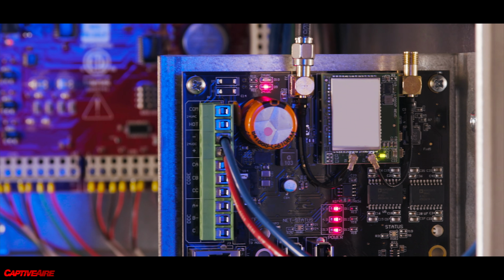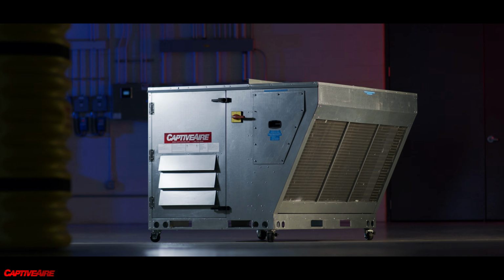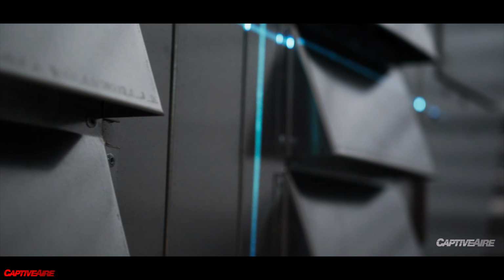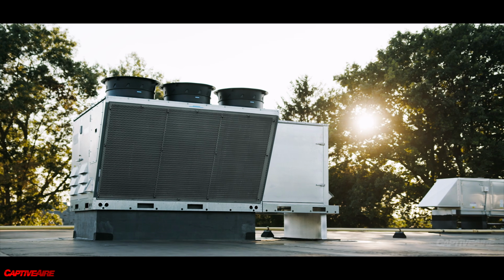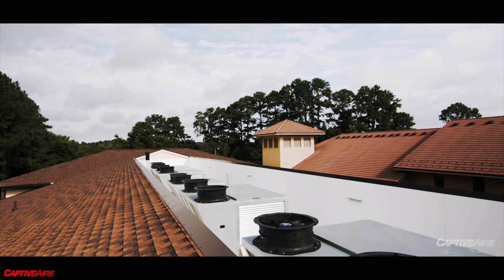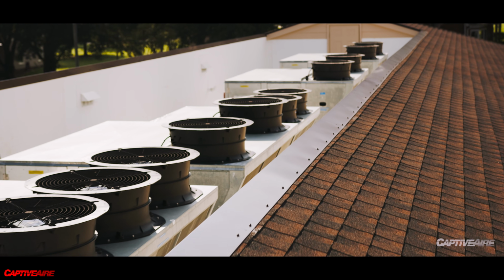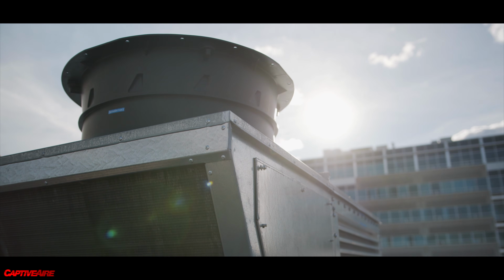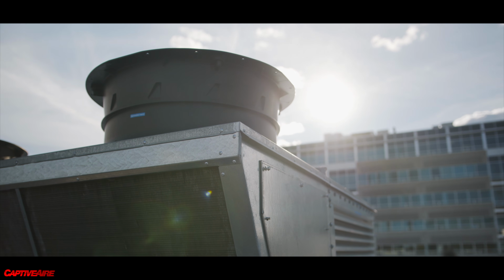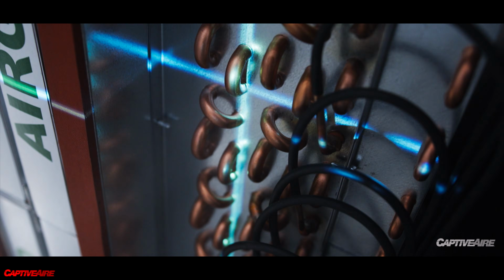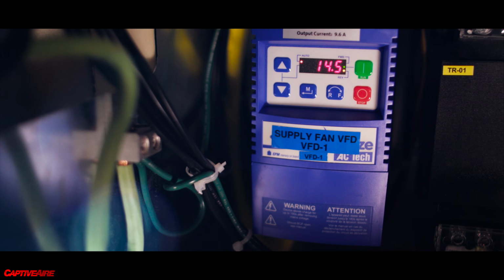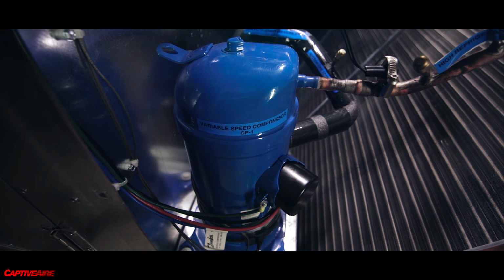This software works with all of our products, but today we're choosing to focus on how CASLink is used to monitor and control our Paragon HVAC units. Paragon is a product that's evolved over the years for us. And from the onset, we were looking at designing this around being a true dedicated outdoor air system, or a DOAS unit. Meaning, all right, we can handle 100% outside air, and everything needs to be able to modulate because we're dealing with very different outside air conditions at all times. And when you're processing outside air, it has a lot of load to it, so you want to make sure you're using as little energy as possible.